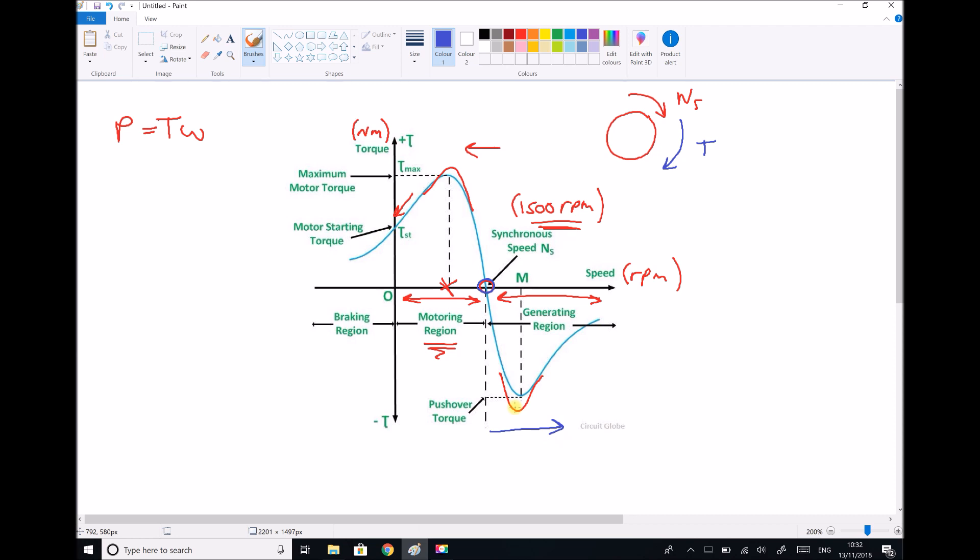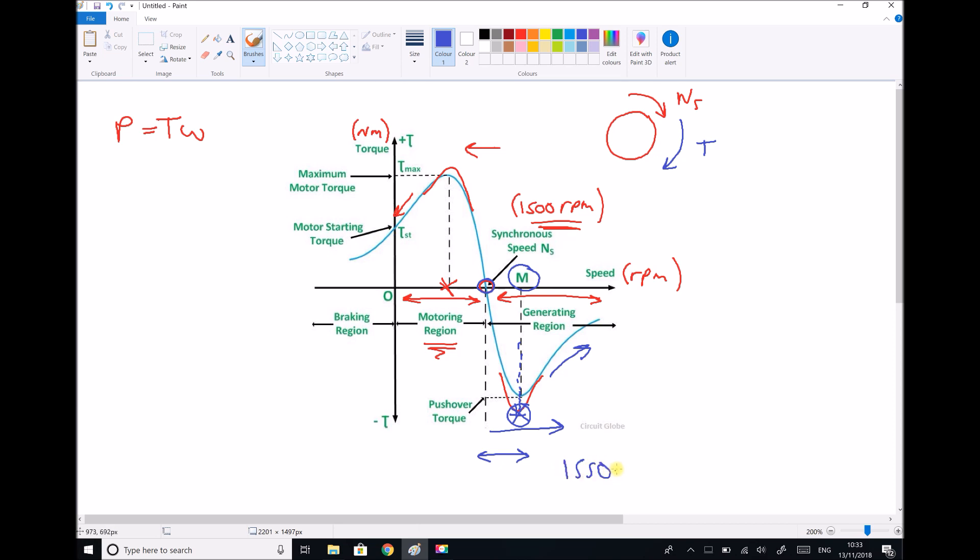Once again, we can see that there's an optimal speed. It's marked on this diagram with a letter M. At that optimal speed we're putting in the maximum amount of torque that the machine can resist. If we were to continue speeding the machine up past that point, the machine's going to produce less torque and hence less power. There's no benefit in us going at a speed higher than the speed labeled M. Once again, this is called slip. Let's say for argument's sake that our maximum power production occurs at 1550 RPM. What that means for this particular machine is that we want to spin that at 1550 RPM or as close to that as possible. If we can spin that machine at 1550 RPM, we have the potential to produce the most electrical energy.